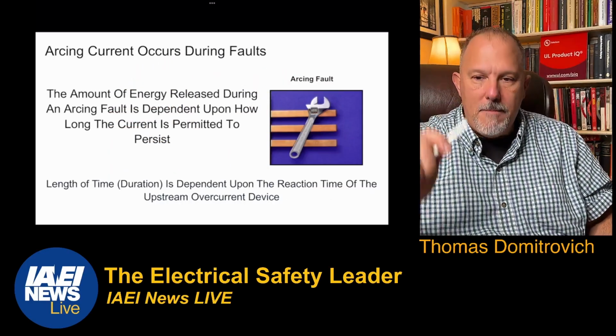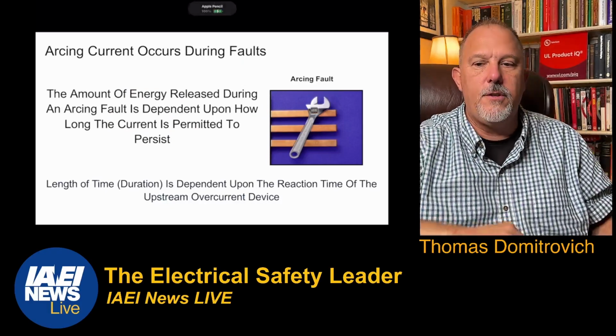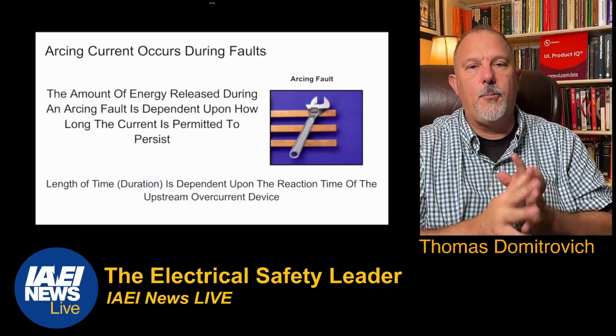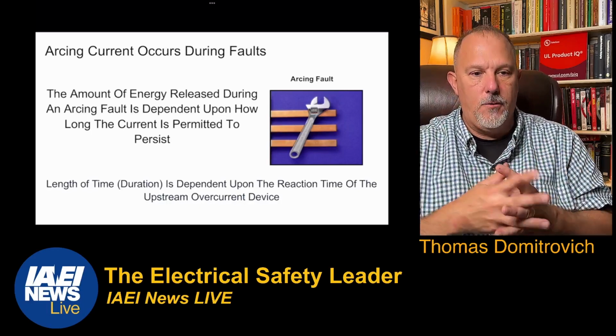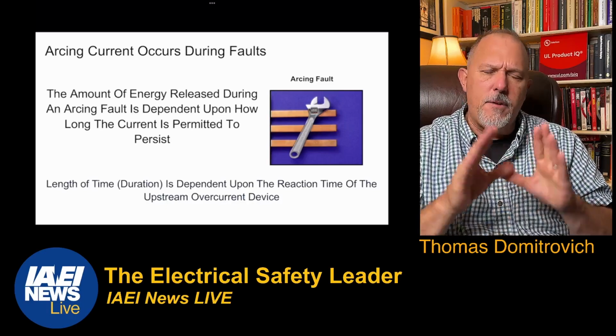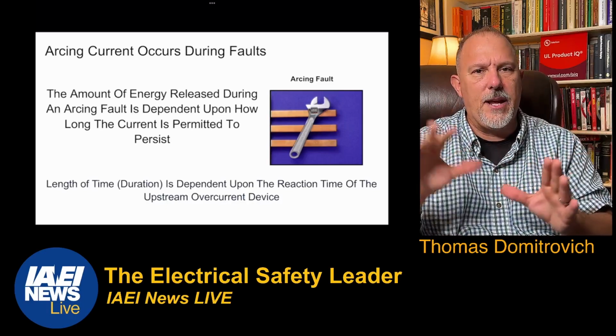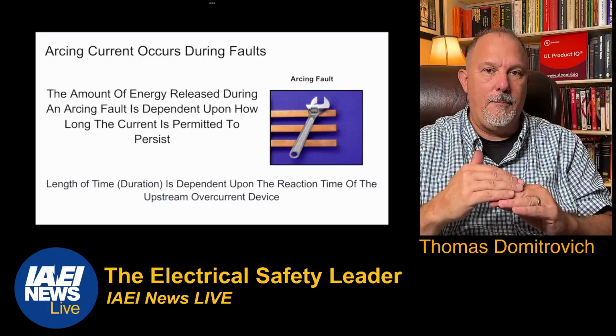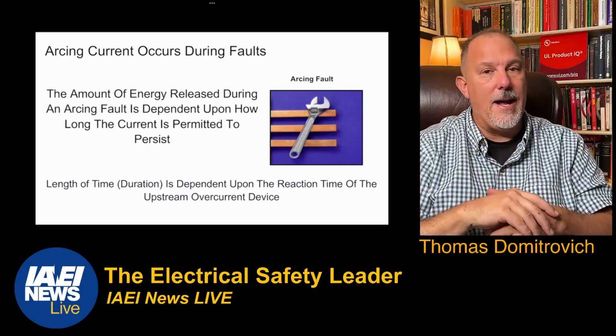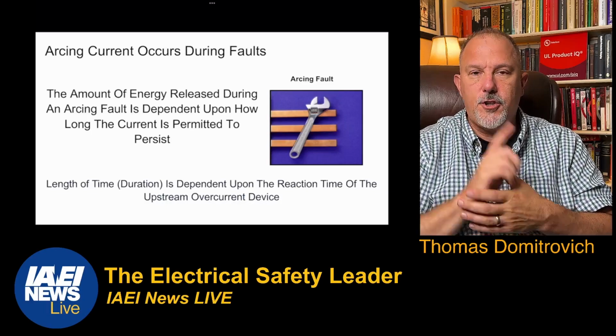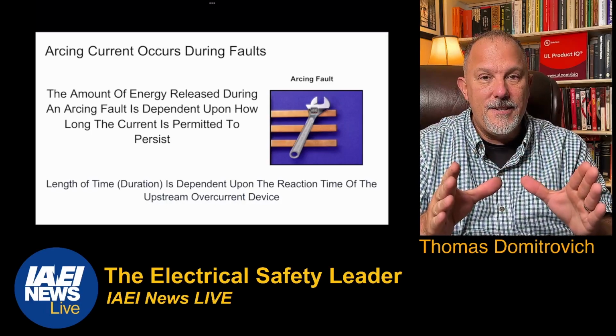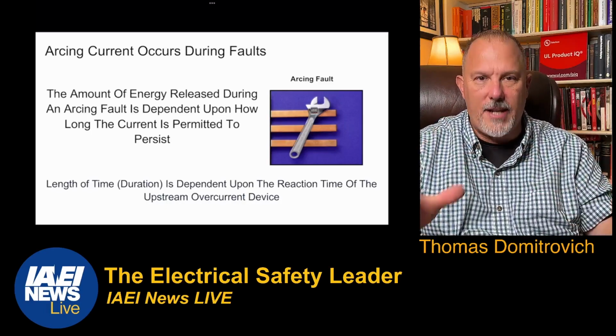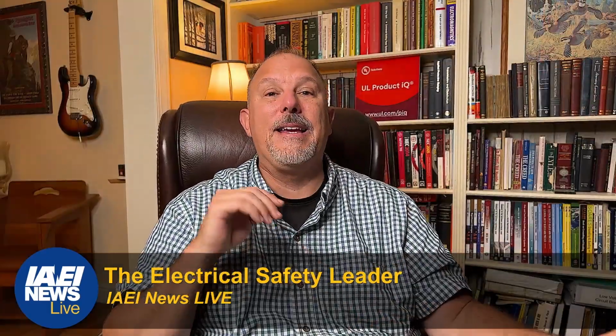Keep that in the back of your mind, because as we move forward, hopefully you're going to start to understand that. So the amount of energy that is released during an arcing fault or during an arc flash event is dependent upon how much time we let the current flow. Remember, incident energy, for the most part, and you'll understand why I'm saying for the most part, it's a little bit later. It's about current and time, how much current is flowing, and really how much time that I am permitting the current to flow. So duration is critical. And it's critical to understand this concept, because I have to understand what I can control and what I cannot control. I may be able to control how much time I let current flow. I might not have too much control over how much current flows.